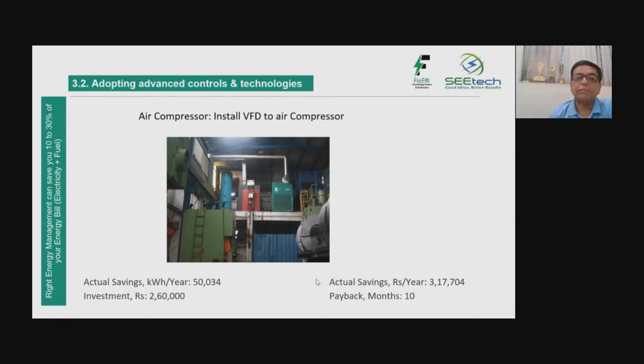These kinds of projects are not such that every compressor should have a VFD. If there is scope for it, one should always go for it. And we can understand this scope by checking for how much time our compressor is actually going on no load.